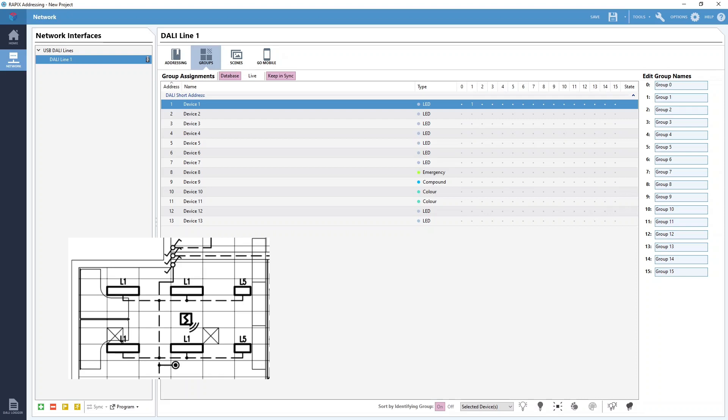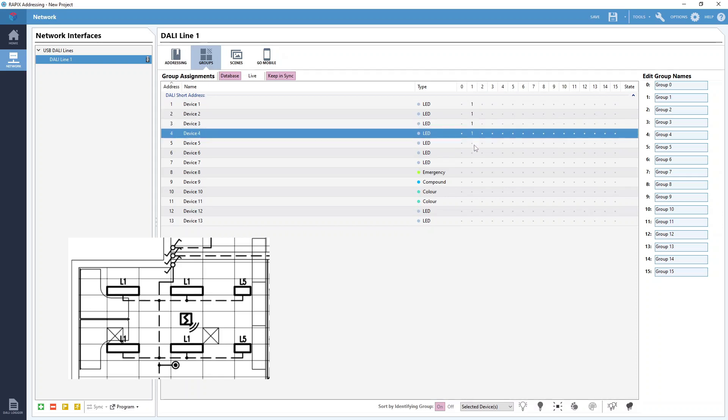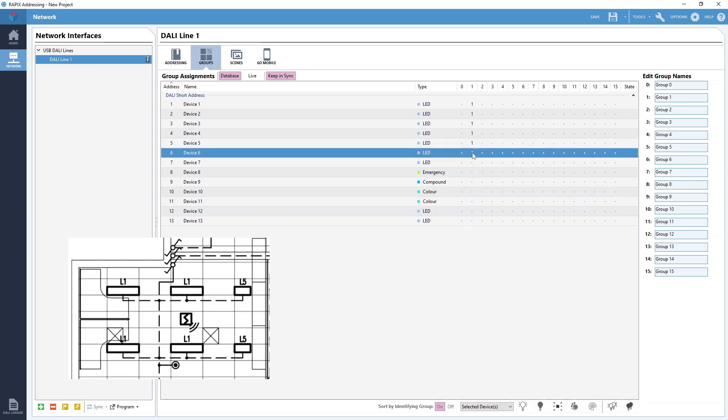So to add all six DALI devices in this room to DALI group 1, we can just keep clicking on the dots here under group 1. And it's as simple as that. The devices are added to the groups almost instantaneously thanks to the keep in sync button up here at the top. While it is selected all changes made here will be updated to the DALI devices immediately.